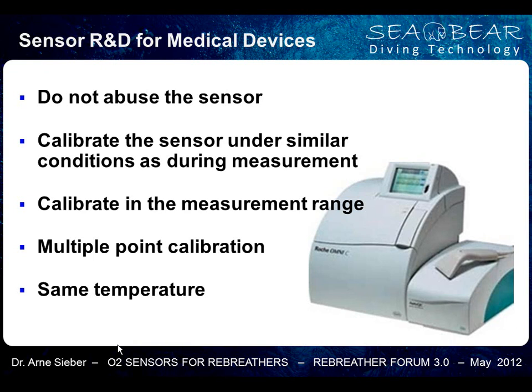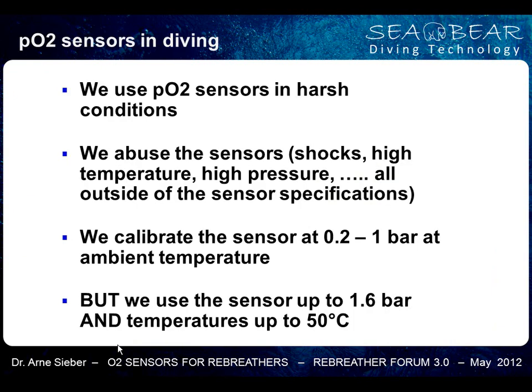But if you compare this now to the oxygen sensors that we use in diving, first of all, we use the oxygen sensors in harsh conditions. We abuse the sensors. With that, I mean we expose them to shocks. With shocks, I mean we put the rebreather on the RIB jumping from wave to wave, and this is not good for the sensors. We expose them to high temperatures, to high pressure. And you have to remember, this is all outside of the manufacturer specification of the sensor.